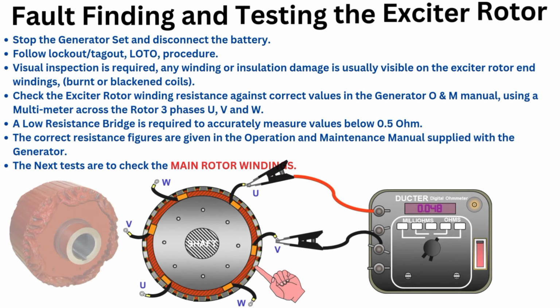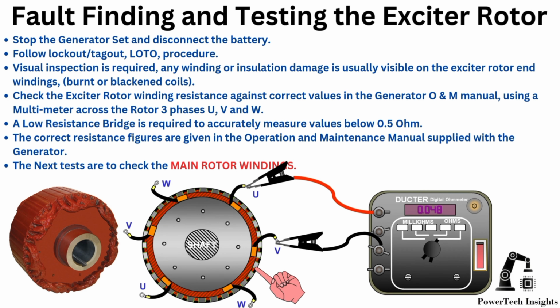Fault finding and testing the exciter rotor. Stop the generator set and disconnect the battery. Follow lockout-tagout, LOTO procedure. Visual inspection is required. Any winding or insulation damage is usually visible on exciter rotor end windings, burnt or blackened coils.